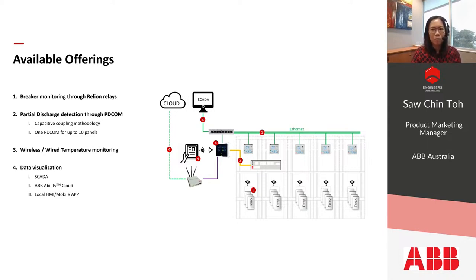The third module, which is the temperature monitoring, can be connected either by wired infrared devices or wireless temperature monitoring devices. They can be installed in the busbar compartments, the circuit breaker compartments, or the cable compartments of the particular switchgear, depending on your requirement. Then all these detection devices will be connected to a SWICOM unit, and the data will be available for viewing through the SCADA system, ABB Ability Asset Manager, the local HMI of the SWICOM unit, or even through the mobile app, which you can install on your tablet or your phone. By scanning the QR code on the SWICOM unit, you can then see the same display as the SWICOM unit. The SWICOM unit is available for connection to the upstream through IEC 61850 communication or Modbus TCP/IP communication.